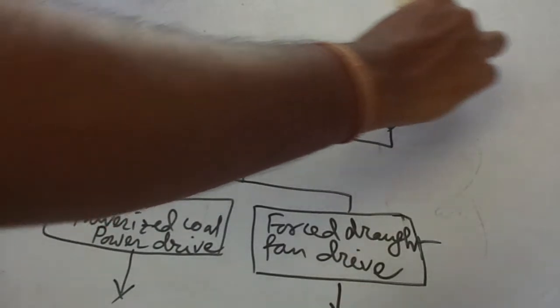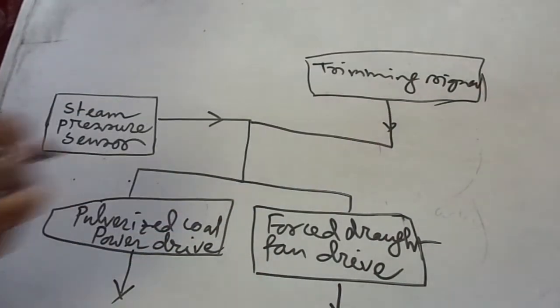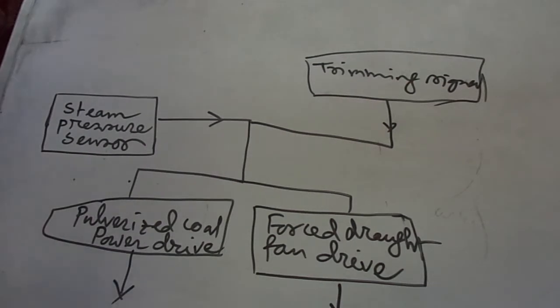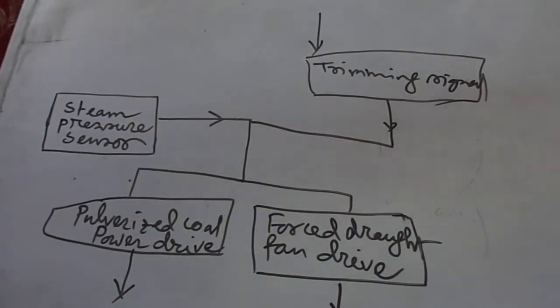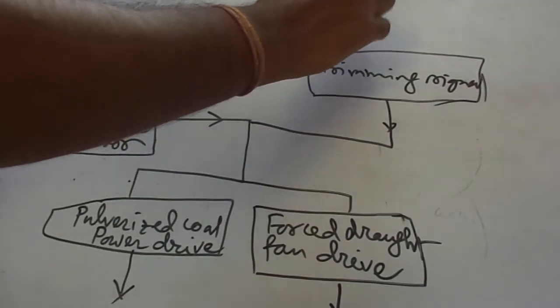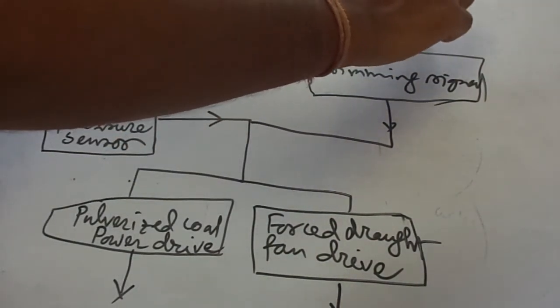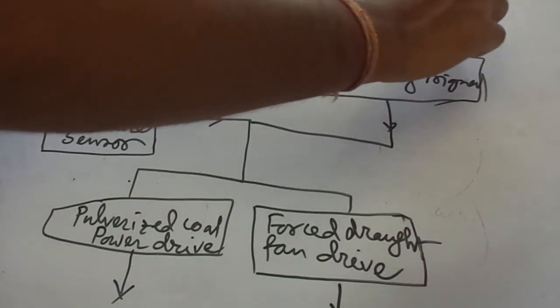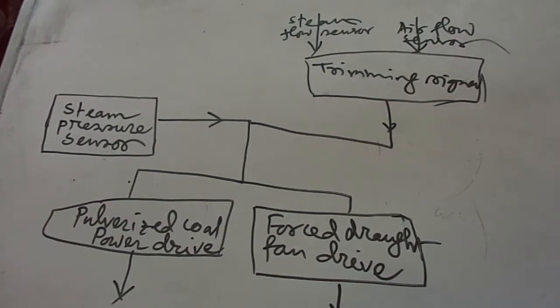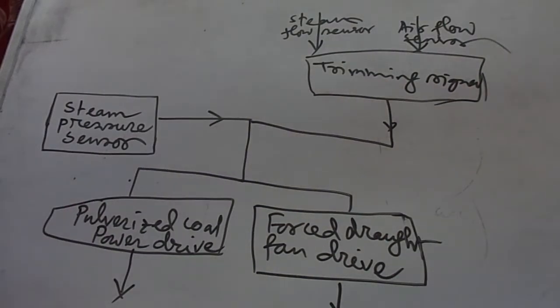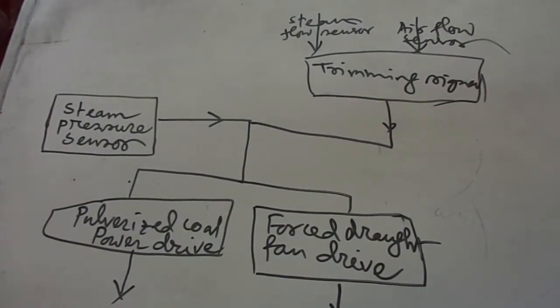Trimming signal: steam flow sensor, another one is the air flow sensor. A trimming signal from fuel flow and airflow sensors maintains the proper fuel air ratio.